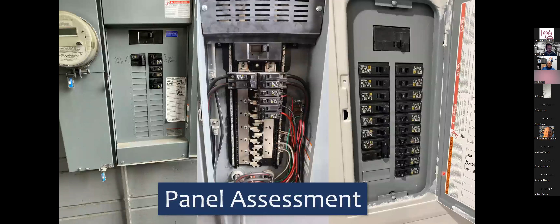Their end goal is that they have gone completely net zero. They put up enough solar and battery to completely cover all the loads we installed, and we had them disconnect their gas meters, so they're now 100% clean energy electric. It was a nice big job. Fortunately, this house had a really nice 200 amp panel - when they did the split of the two units, they put a 200 amp panel in.